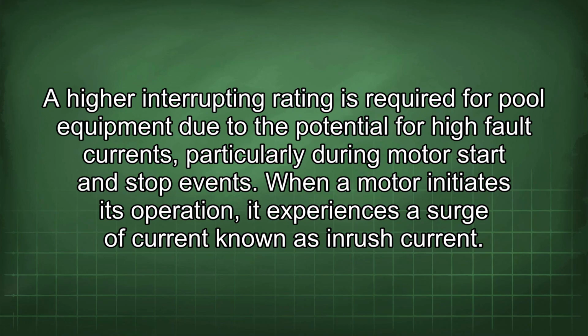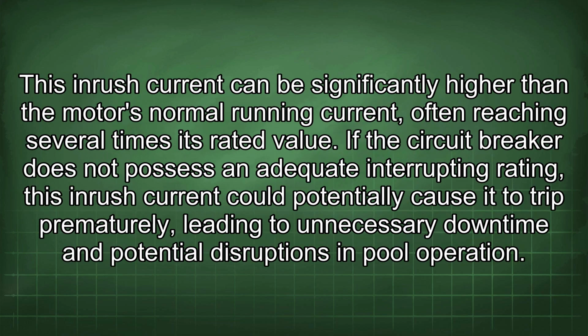Higher interrupting rating is required for pool equipment due to the potential for high fault currents, particularly during motor start and stop events. When a motor initiates its operation, it experiences a surge of current known as inrush current. This inrush current can be significantly higher than the motor's normal running current, often reaching several times its rated value.